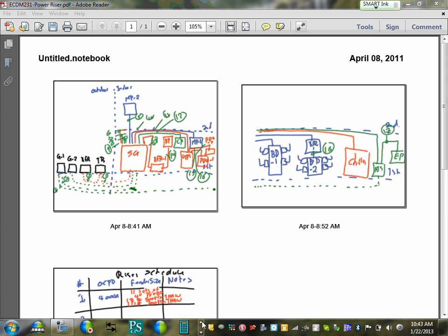Anybody have the load calculator in front of them? Okay, so what's the largest panel that we have? The MP1, 600 amp. And what's the biggest breaker? Not the feeder breaker, but you're not feeding the busway on those panels. Most of them are feeding 100 amp. So the biggest breaker in this panel is 100 amps, and we'd be looking at a standard lighting panel at that point.